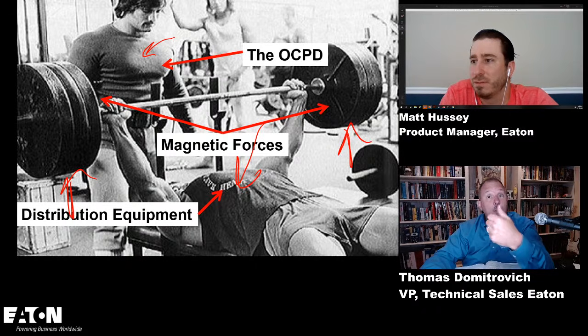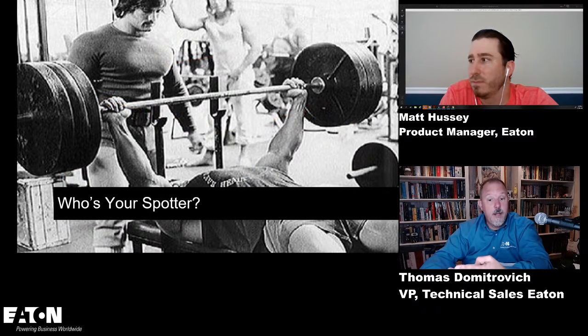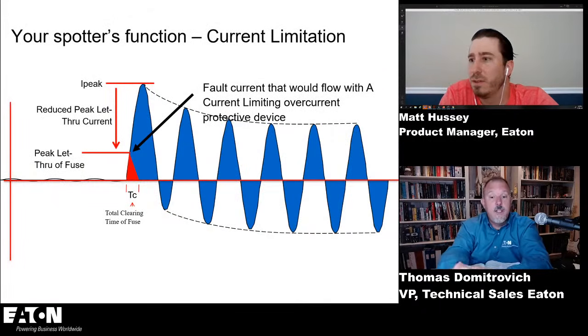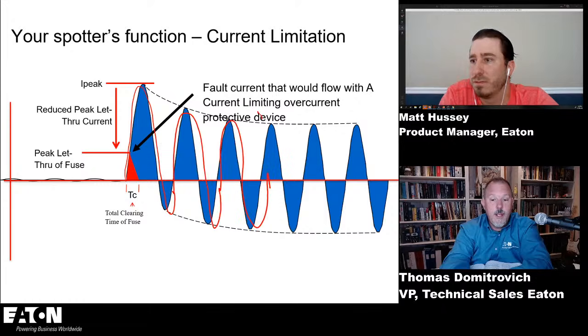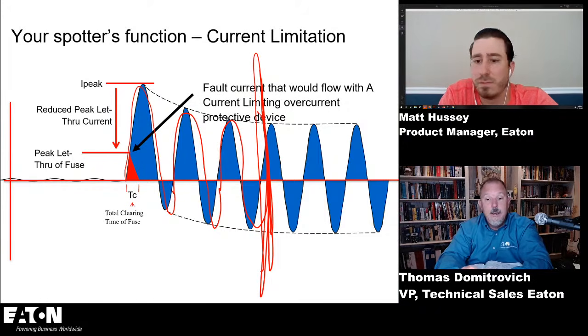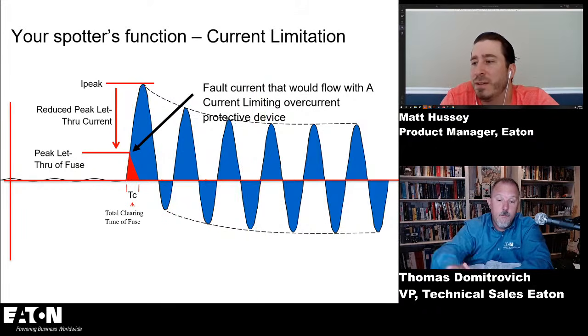And we know, based upon what you told us, Matt, it's a 3-cycle withstand rating, right? That's correct. So that says I can only stand 1, 2, 3. That is it. If you let more than those 3 cycles flow through that MCC, we could experience some bad things, right? Yeah. That's where we go back to, even the compartments. I think your example kind of shows that really well with the fault current flowing through and the equipment has to hold it together. So that's really important with all those short circuit current ratings is that equipment is designed to still handle it and hold it together.